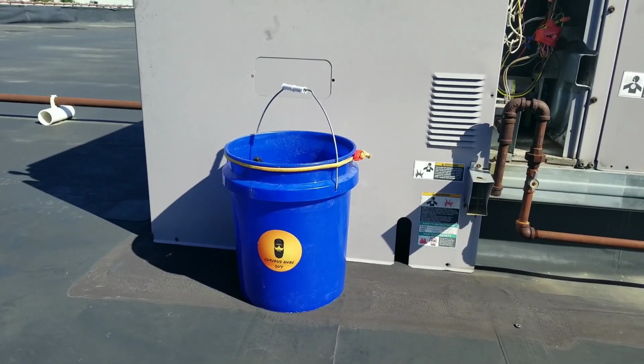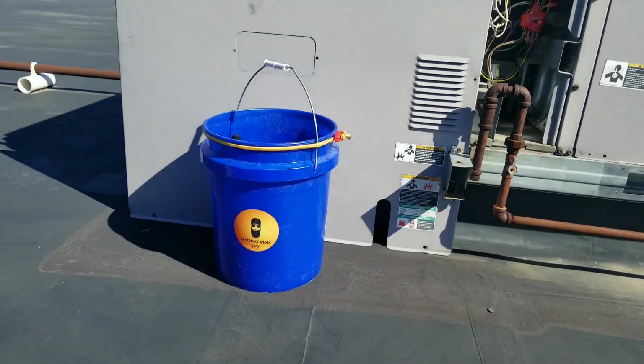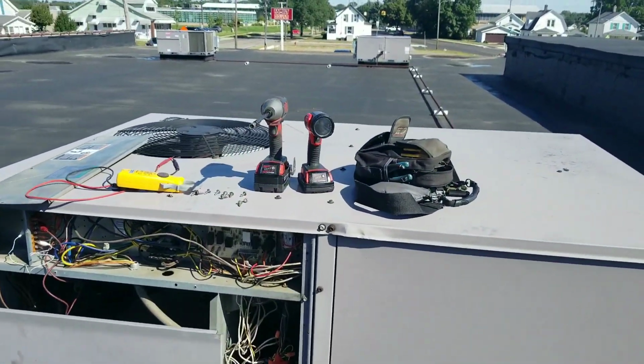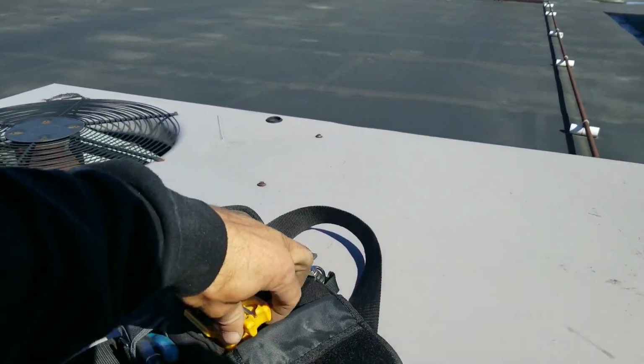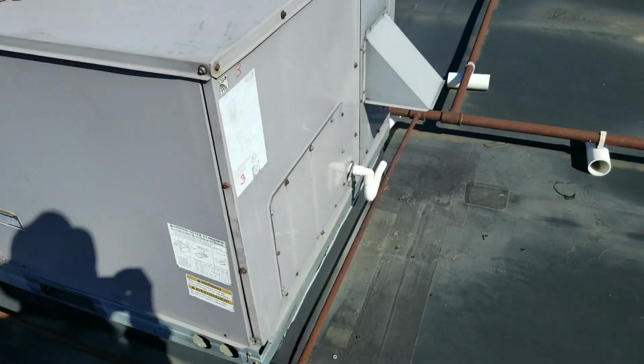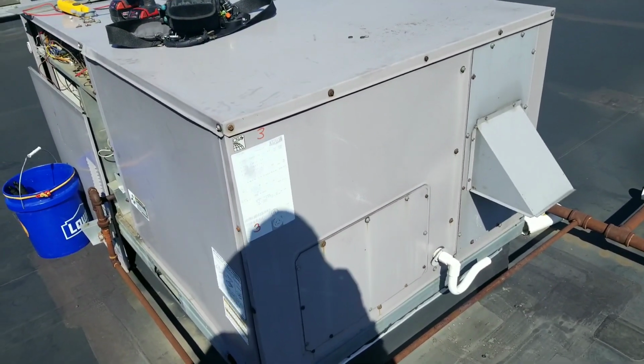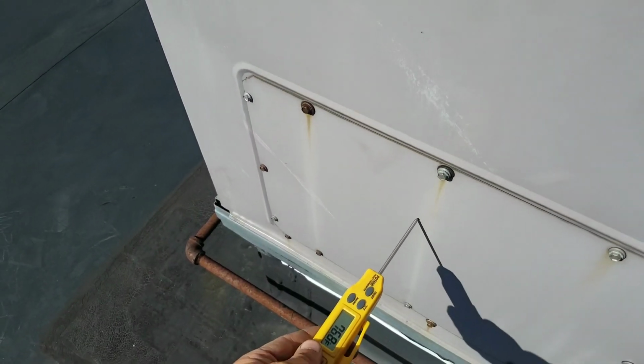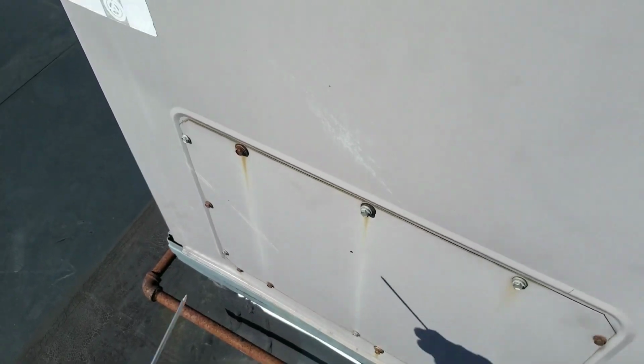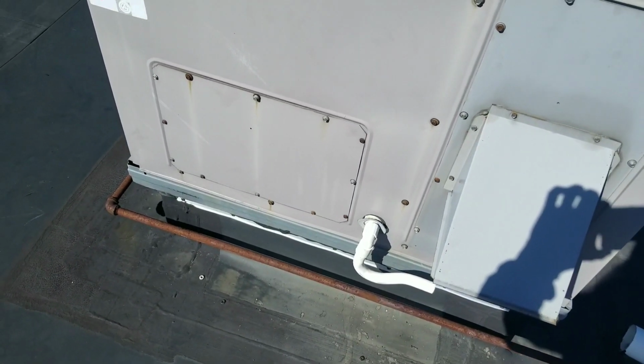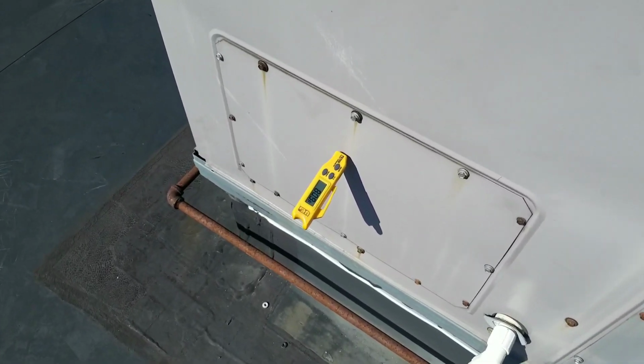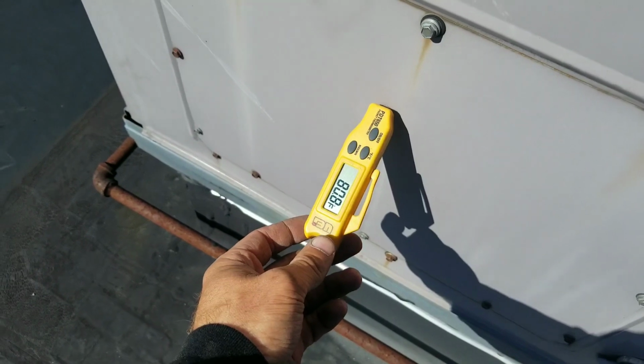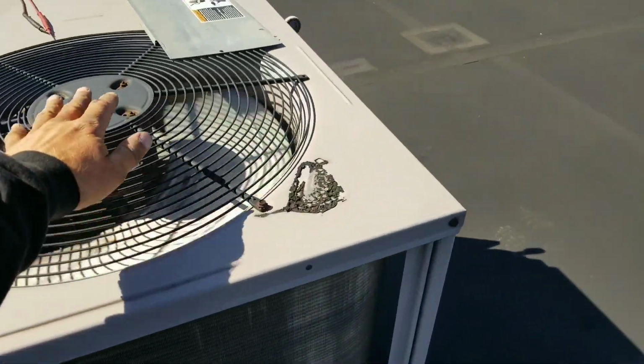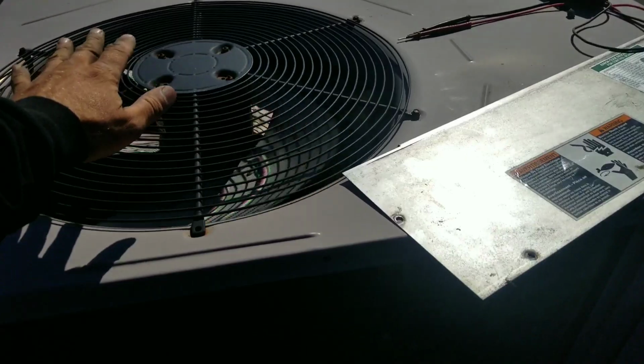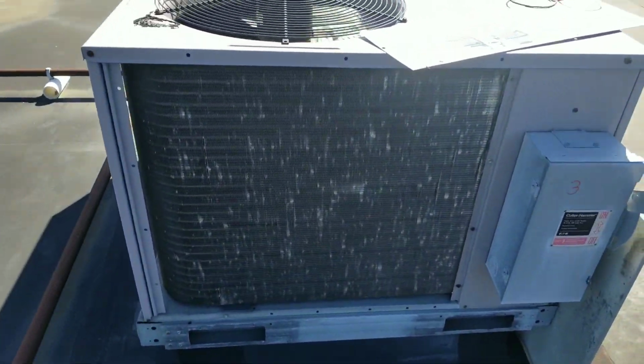Notice my branded bucket there, my Curious HVAC guy bucket. Anyway, we're cooling, we're running. We haven't tripped a breaker yet. Let's go over here and get a supply temp. Well, not gonna get a supply temp that way. Starting off at 80. Not a whole lot of hot air coming out of there.